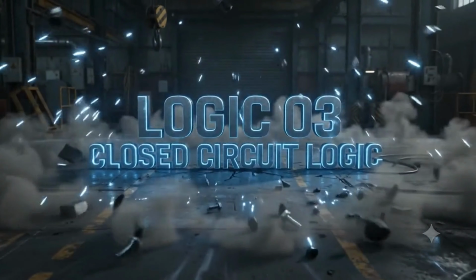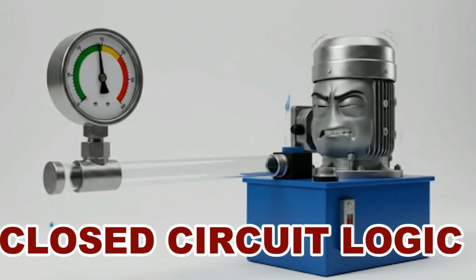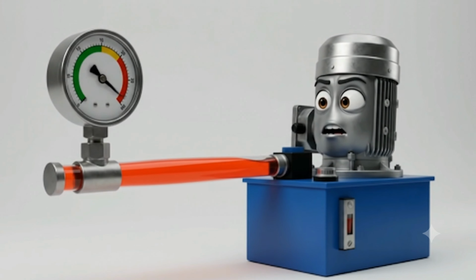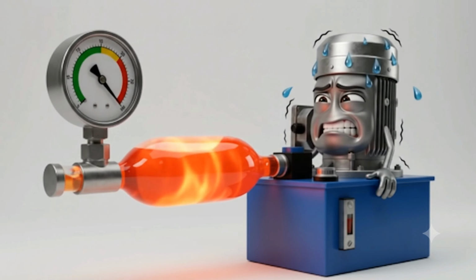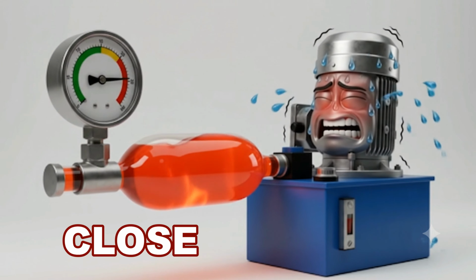Troubleshooting logic number 3, the closed circuit logic. To build the correct pressure, the oil's path from the pump directly to the actuator must be a completely closed circuit. If this path opens up anywhere, like a hidden internal leak, the resistance required to build pressure will never form. Why? Because the flow completely escapes through that exact open location. When troubleshooting, your mission is to logically trace and expose exactly where this closed circuit has opened up.